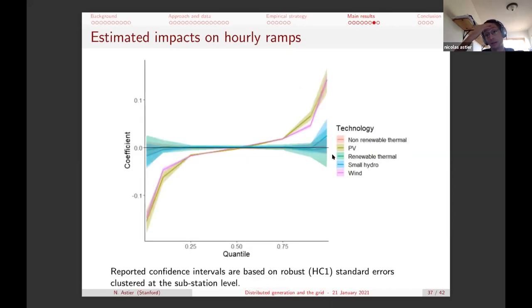What's more surprising again, and quite disappointing, is that for wind and PV, the addition of more megawatts of wind and PV generation tends to rotate the curve in the bad direction, if you wish. In the sense that it tends, on average, to amplify the magnitude of hourly ramps you see locally. So if you take the 99th quantile or first quantile, adding 1 megawatt of wind or solar, we estimate, increased on average over the population of substations the most extreme ramp by 0.15 megawatt.